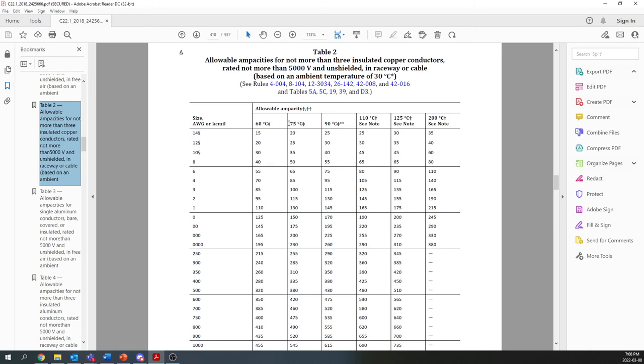You have to look at your boundary conditions, and rate your system to the most limiting or most conservative boundary condition. So in this case, of course, it's 75 degrees. So we have to use the ampacity values off of the 75 degrees column. You'll just get used to doing that if you go to table 2. All these other columns are not really used very often, except in some special cases. Now, if there's a piece of electrical equipment that has a 60 degree termination, or some other rule in the code, since there's a bunch of rules you have to follow when using this table, and the equipment is only rated for 60 degrees Celsius, then you have to use the rating off of the 60 degree column. But in general, we pick 75.